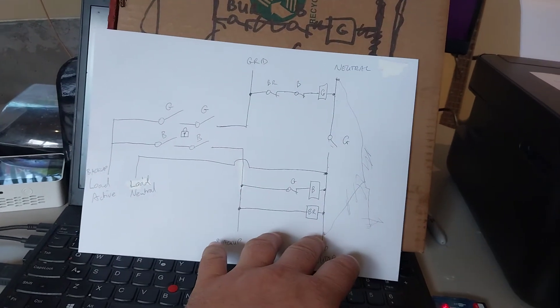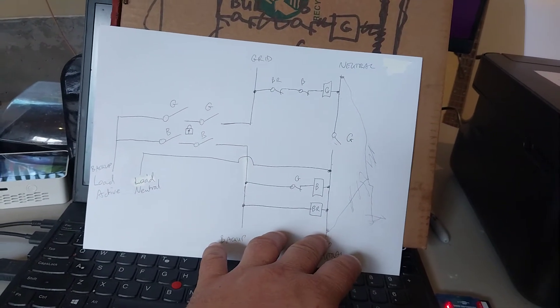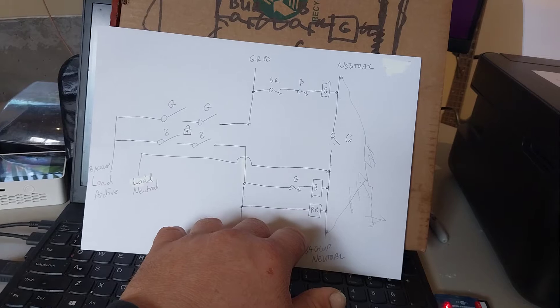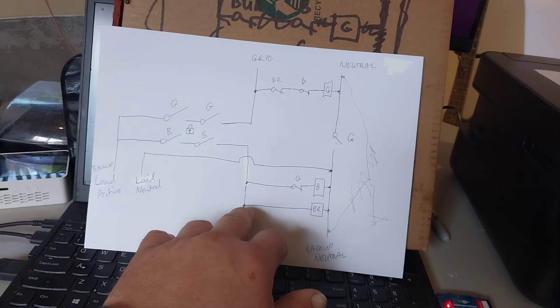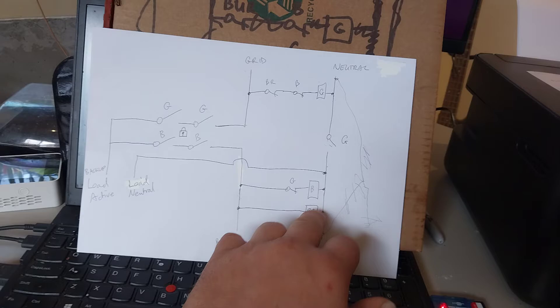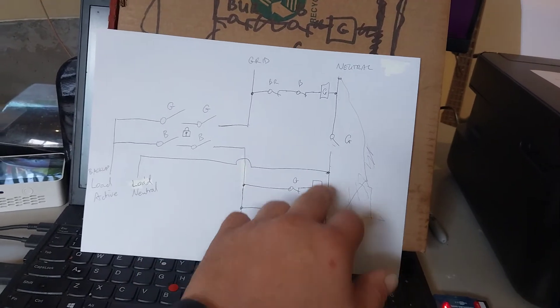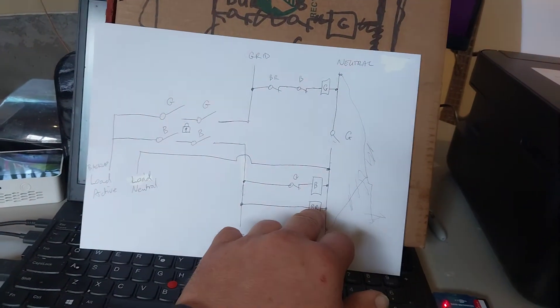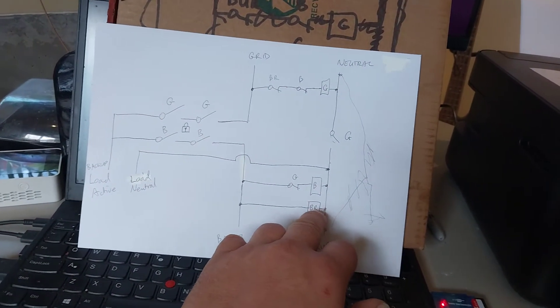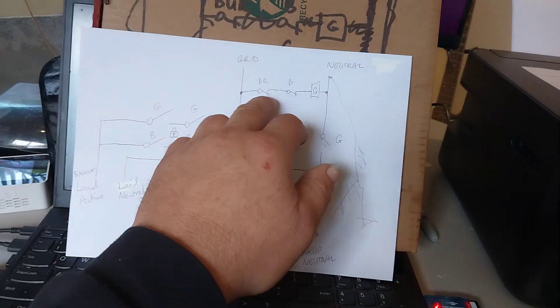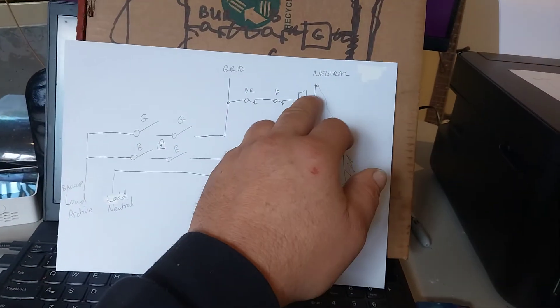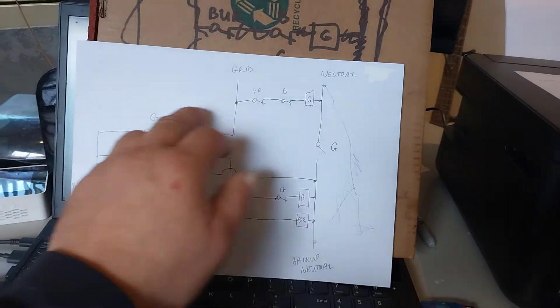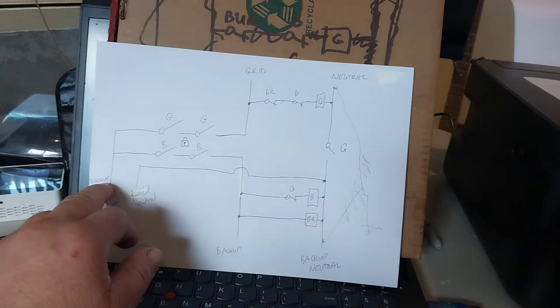If there's a problem here and the inverter fails, well and the backup power supply is failed, well then obviously these coils will de-energize both the backup contactor and the backup relay and these will close allowing the grid contactor to pull in and supply power to the load there.